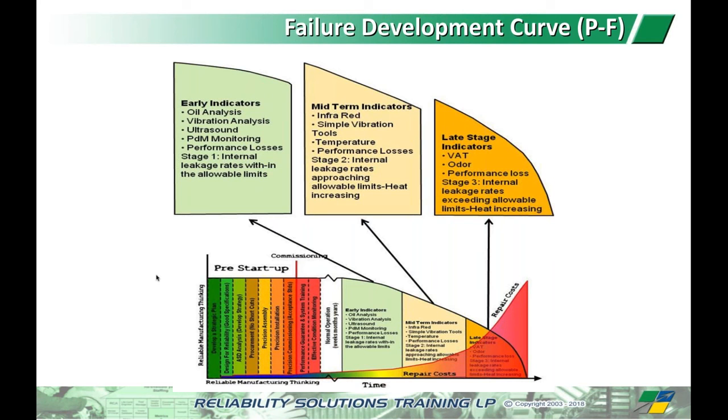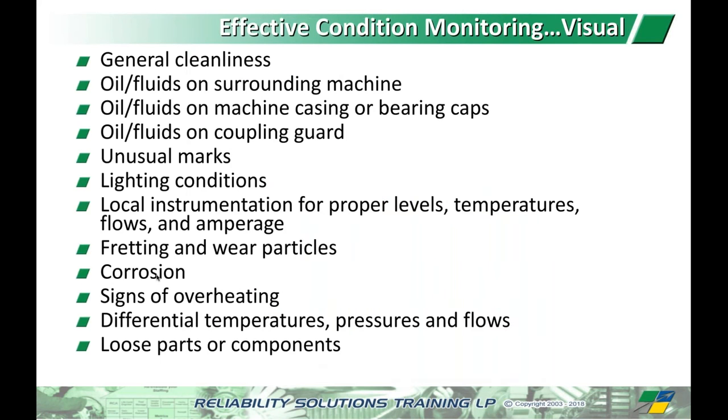And of course, also wrapped up in that condition monitoring is performance monitoring as well. Looking at visually, again, you guys don't need me to tell you what good looks like. I don't have a whole bunch of photographs here of good and bad. I think we all recognize what good and bad looks like, but general cleanliness, obviously, if it's dirty, covered in dust or stock or ore or something like that, then it becomes very difficult for heat to transfer out.